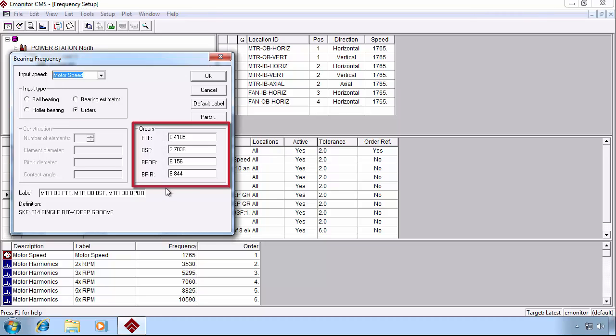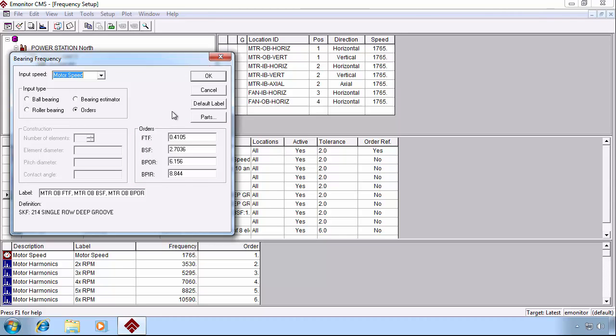Ball spin, ball pass outer race, inner race, cage frequency. These are all defined as orders of running speed. This data is usually readily available from the manufacturer's specifications.